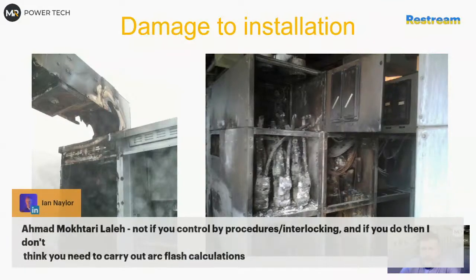So you have some discussion here, but again, it really depends how it is done. If you cannot open the panel at all, so you have all the interlocks like on the medium voltage switchgears, where you physically cannot do it, and it's built in, and no one really wants to do it this way, then I would say at least you need to check if your arc rating is proper. So you might skip this panel, but you have to do a calculation for everything else.